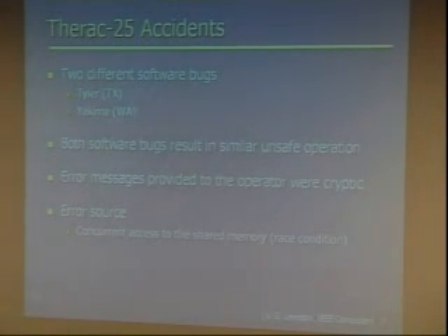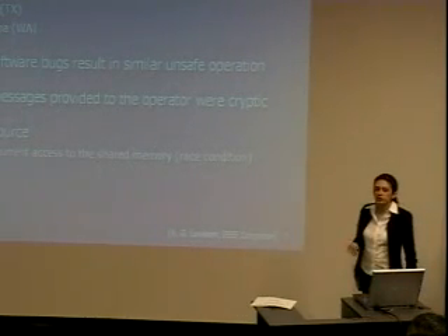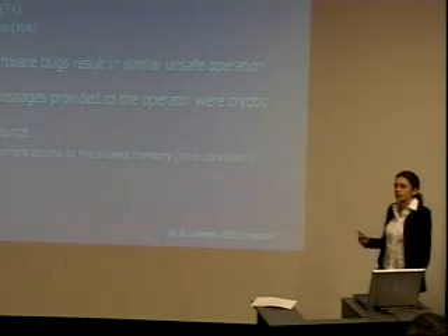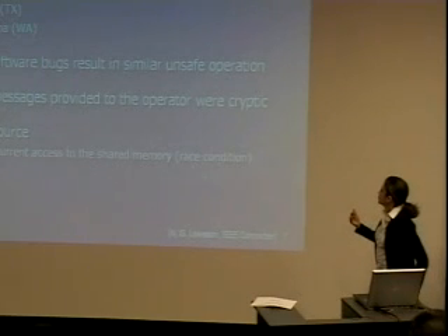After all the analysis and the recall of this system, 2 important bugs were found in the Therac-25, which are known as the Tyler bug and the Yakima bug. Both of them resulted in an unsafe operation, which means that the turntable was not in the correct position in the beam path. For example, we wanted to produce the X-ray mode, but the equipment between the beam path and the patient was not the right equipment. Although at the time these bugs appeared there were some messages given to the operator, saying for example that the system is malfunctioning, the error messages were cryptic. That means that the operator didn't have any idea what the error meant. So the operator just proceeded with the operation.